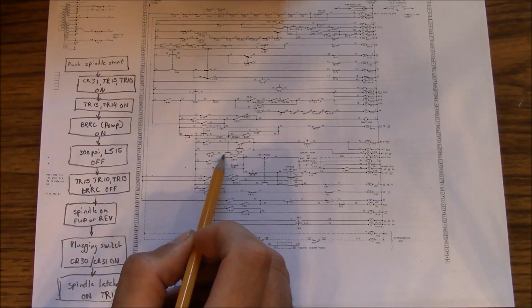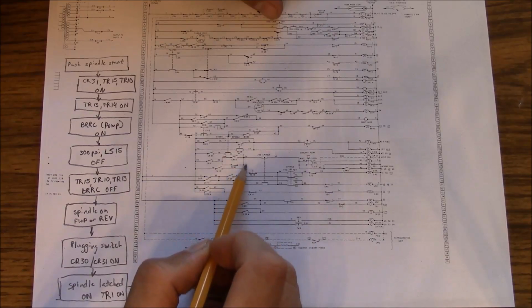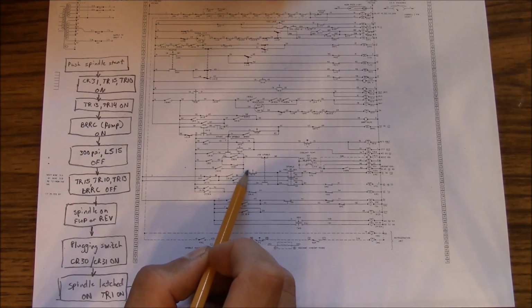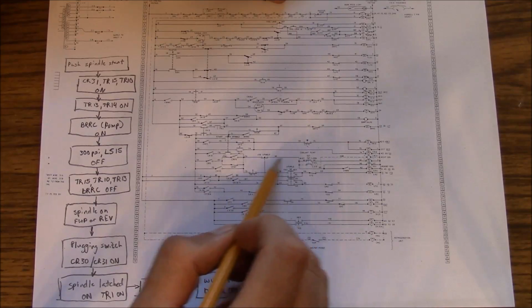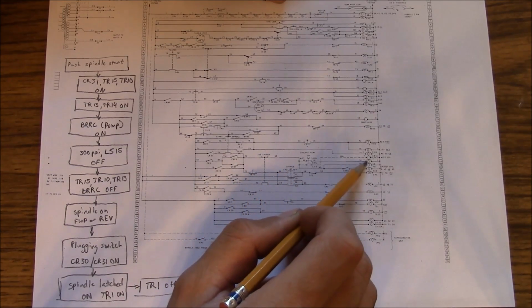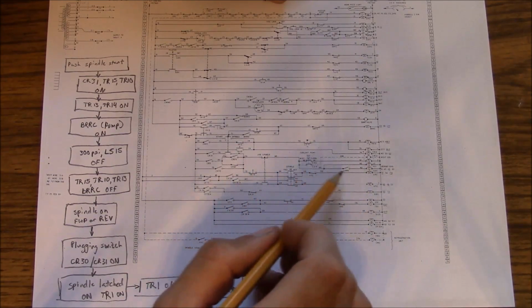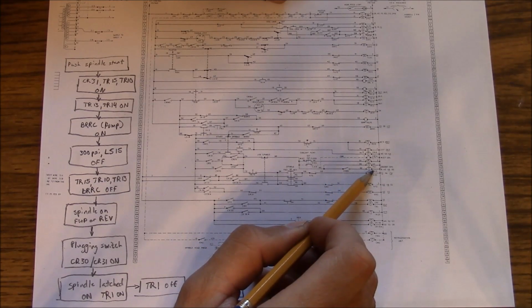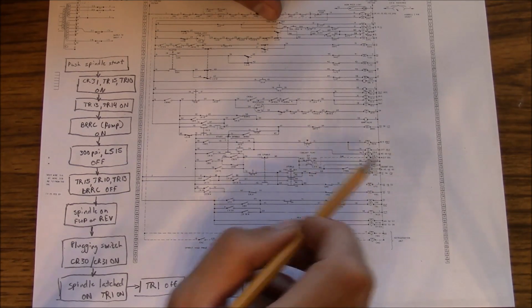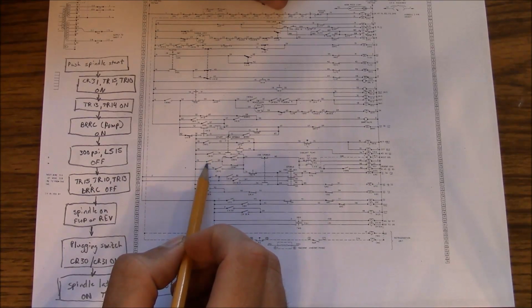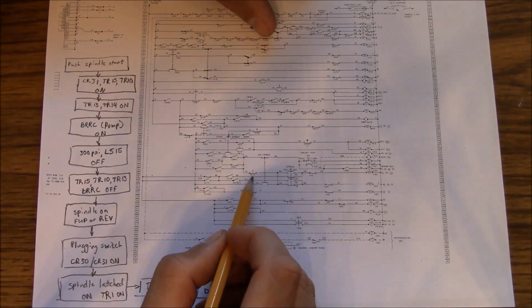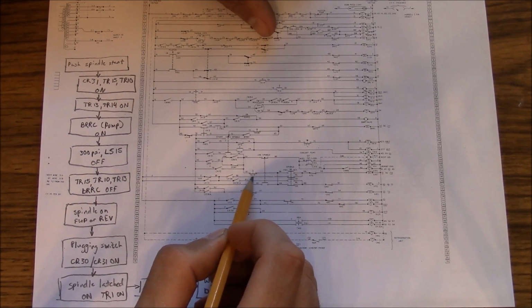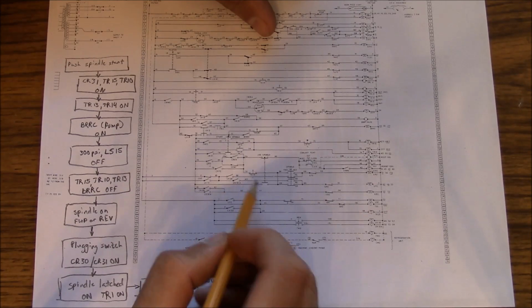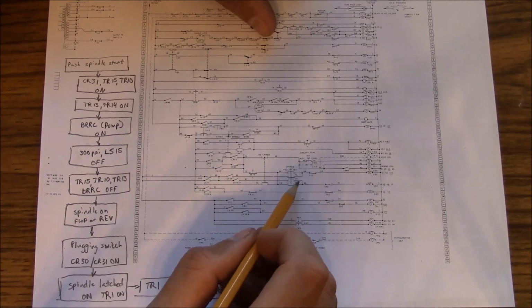CR31 is right here. As soon as it's turned on, it allows power to go through this way, through the spindle jog switch, which is closed, over here to some of these other relays that aren't really used very often, but it does turn on CR5, and CR5 is right here. So this is going to be closed, and then TR15 here, this is a normally closed contact. On the TR15, that's going to open up, so that's going to prevent the spindle from running for right now.